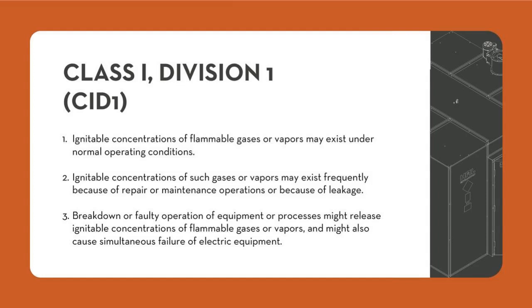So having those concentrations of vapor in the room is more dangerous than having concentrations of liquid solvent in the room. It's dispersed through the air, so you have this large surface area to volume ratio of those vapor particles, making them highly combustible, and they can really cause an explosion if you're not using the proper rated electrical and proper ventilation. But the C1D1 aspect of this just covers the electroplating. So that's C1D1. What you have on the screen are the three main conditions set by NFPA 70, which is the National Electric Code, and that's how they define C1D1.